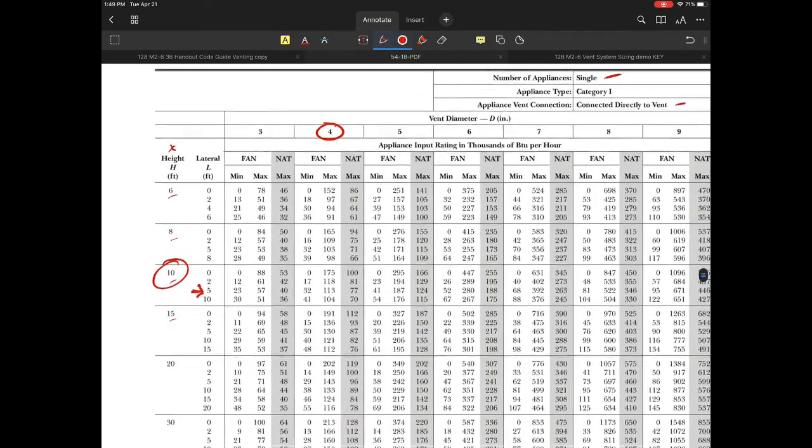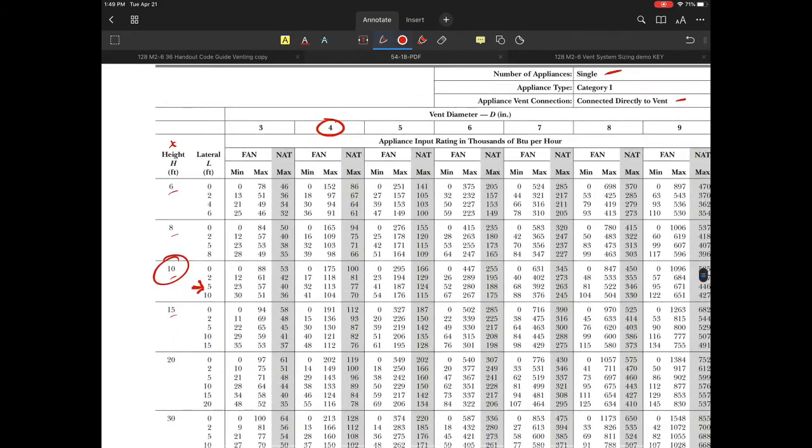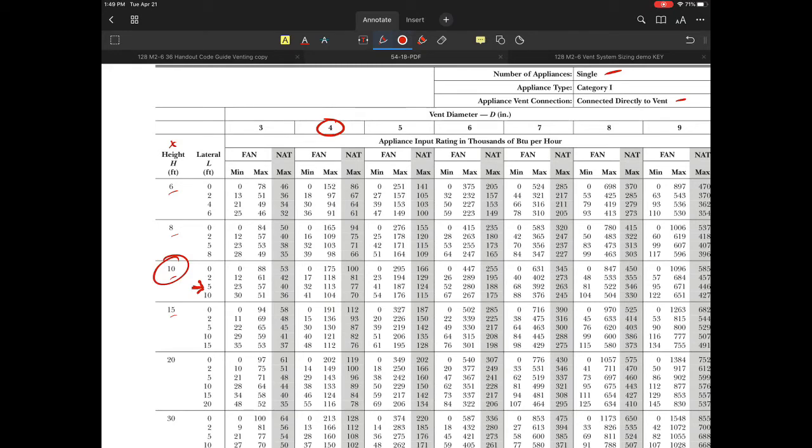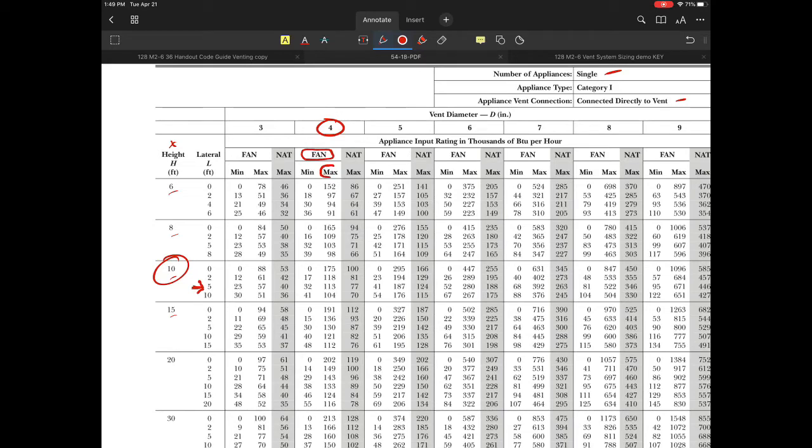If we downsize, we'd have to follow additional rules in the table. But let's start with this. For my 80,000 BTU at 10 and 5, and because this is a fan-assisted appliance, we'll use the fan max and fan min columns.